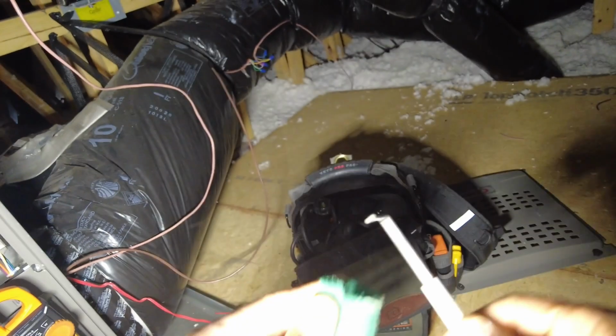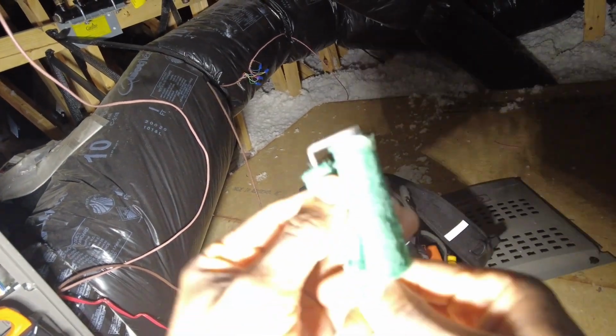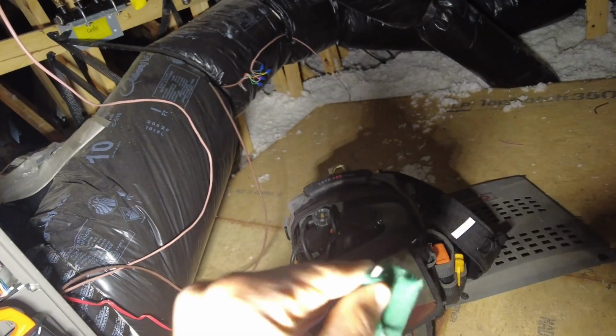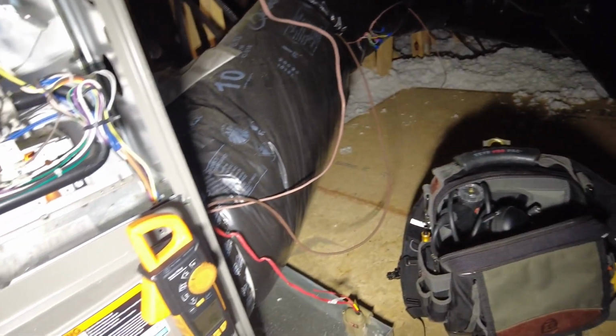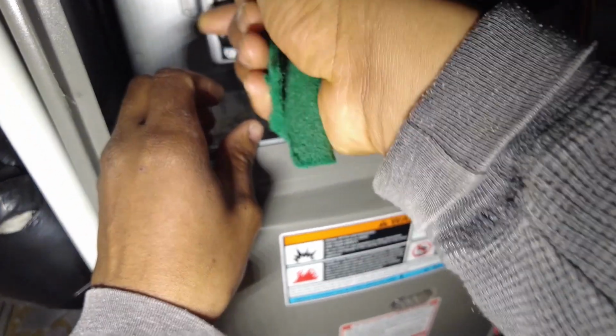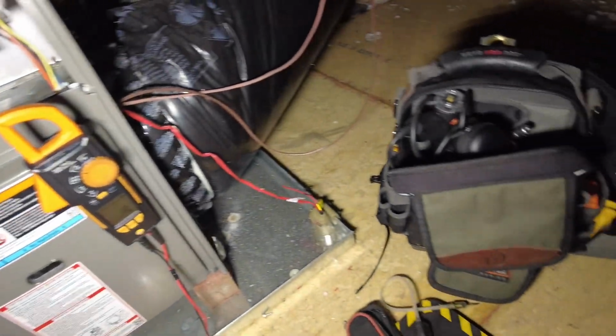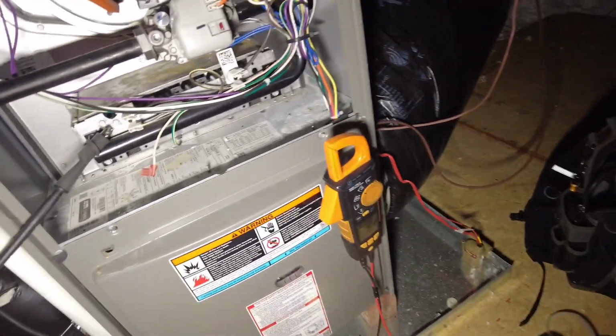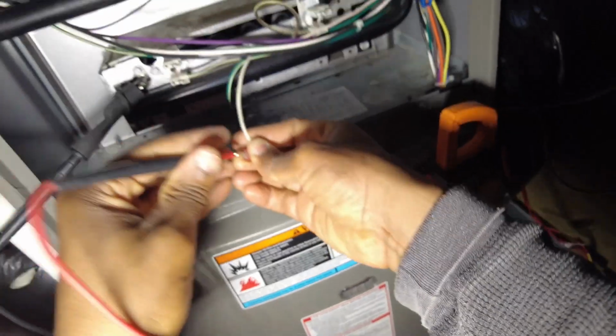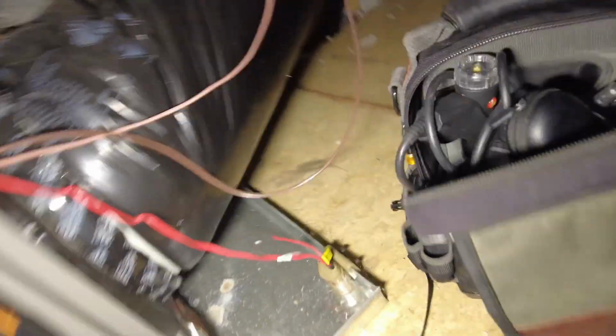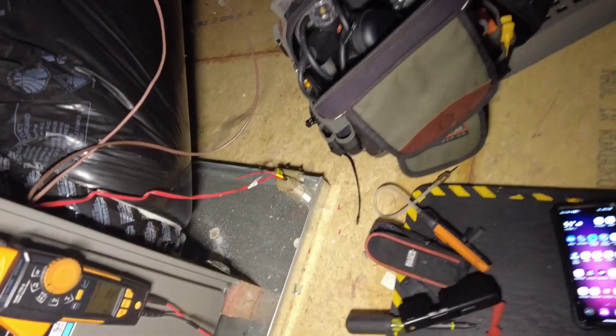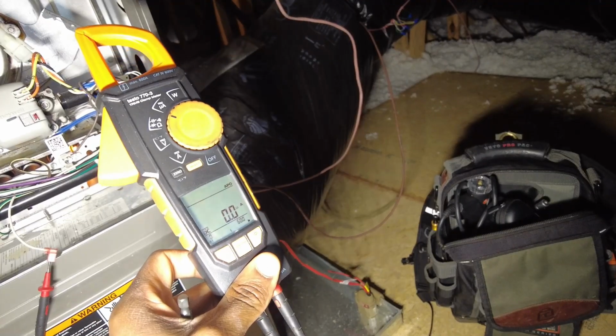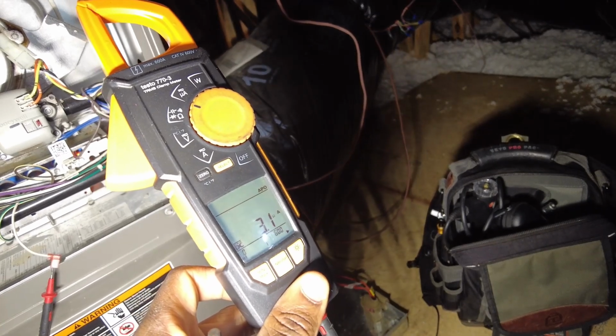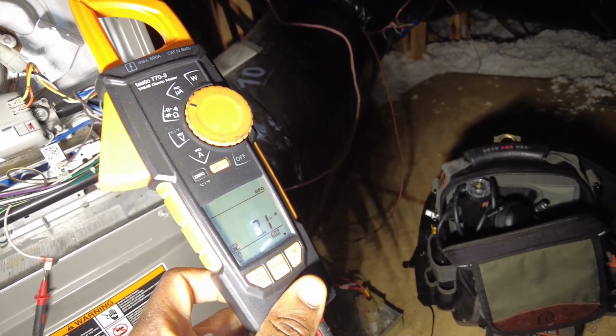Let's do a quick little clean like such. And that might actually give us a little bit more signal. We'll see. I'll test it again after the cleaning. Got that there. Turn our gas on. And then we'll put this in here. Let's see what happens. It's probably not going to be much more because it wasn't that dirty, but if it were dirty, you'd see a significant improvement. Yeah, no better. 3.1.